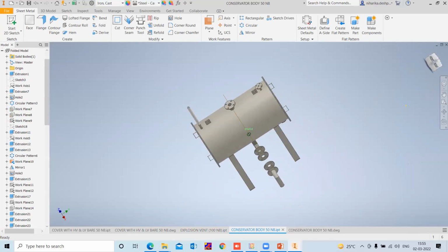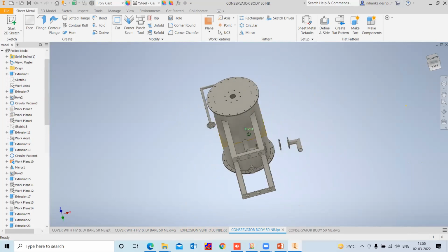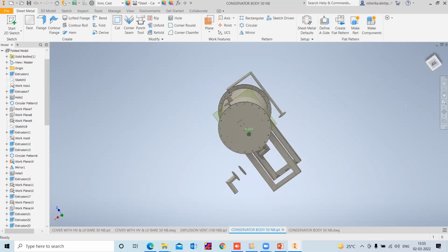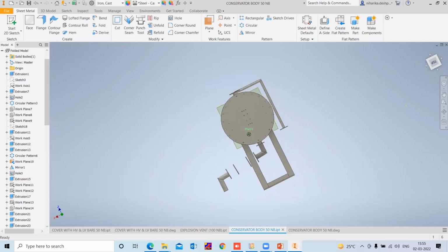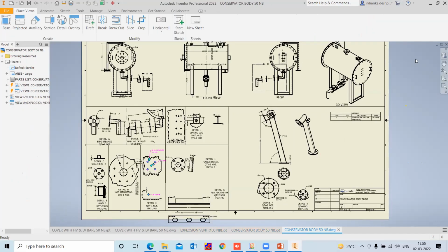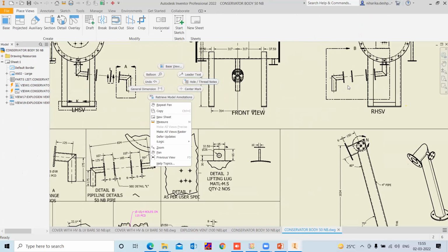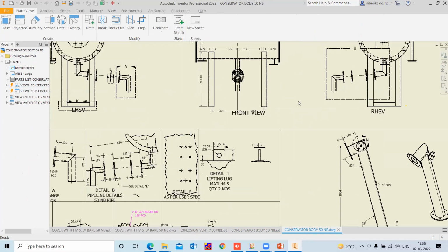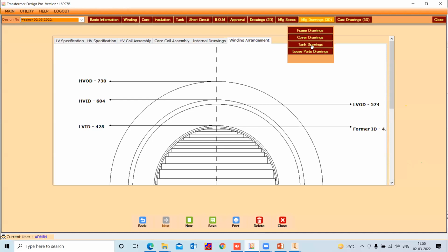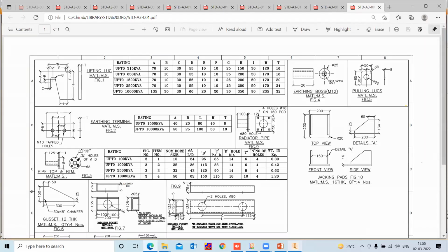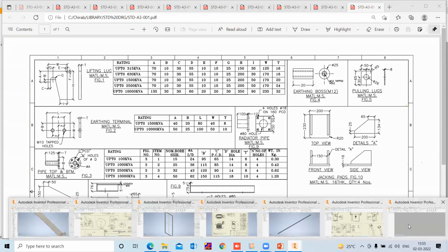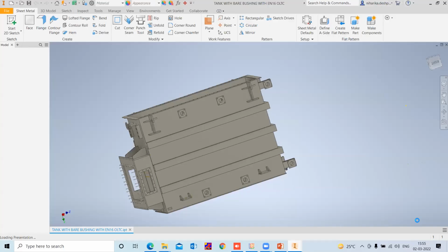This is your conservator. You can see the arrangement for silica gel breather, then the Buchholz relay and valve, and the clamping arrangement on the tank. And the same you will get in 2D also with all dimensions. And this diagram you can also export to AutoCAD, normal AutoCAD. Then next is the tank drawing. So you can see how fast the drawings are generating. Within 30-40 seconds, you'll get all the drawings. It's opening very smoothly.